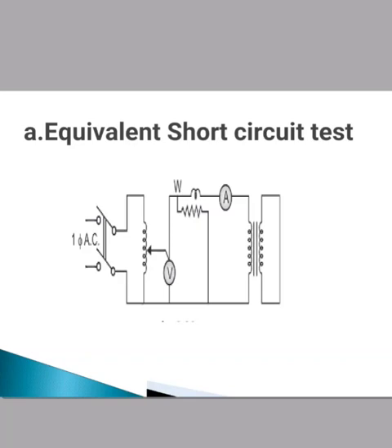This test is carried out on the power transformer, and this test is similar to the short circuit test of the transformer. See in the image. The only difference is that in this test, the short circuit voltage is adjusted in such a way that the wattmeter shown in the figure will record the total loss of the transformer on full load condition. Total loss means the no load losses excluding small no load copper losses, and full load copper losses including stray load losses, etc.